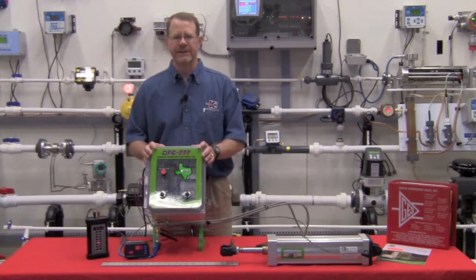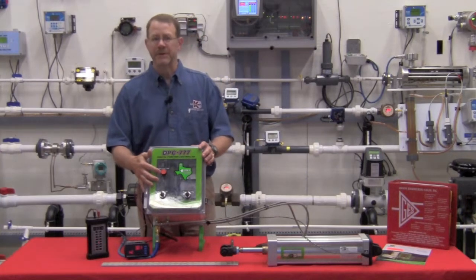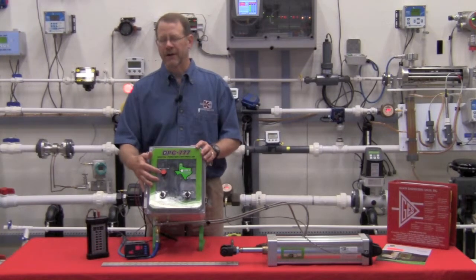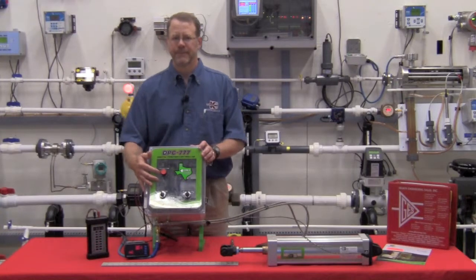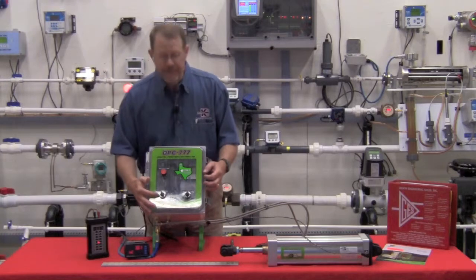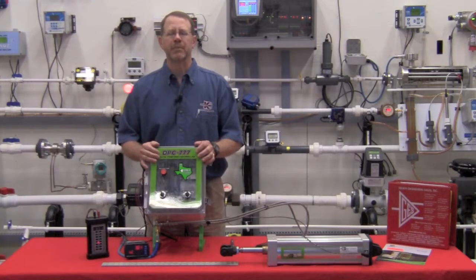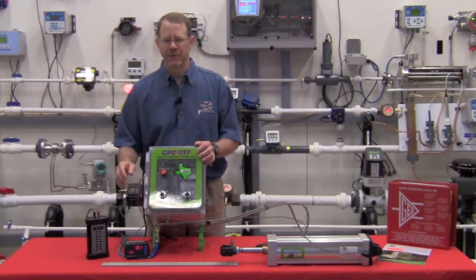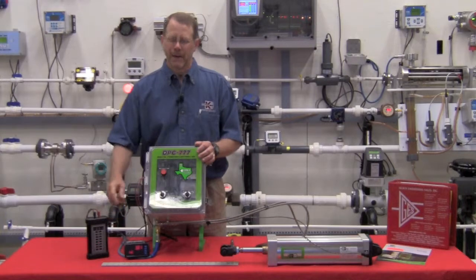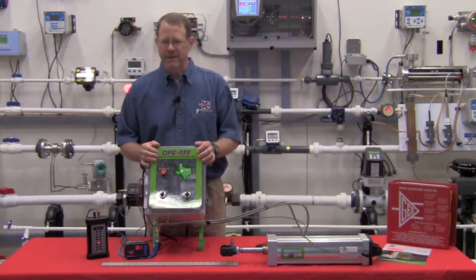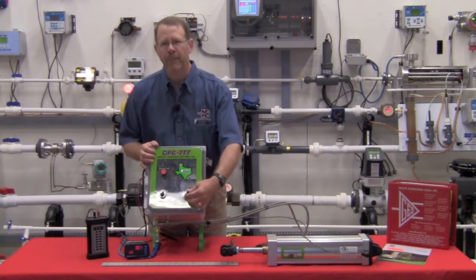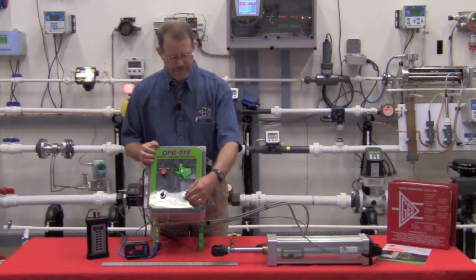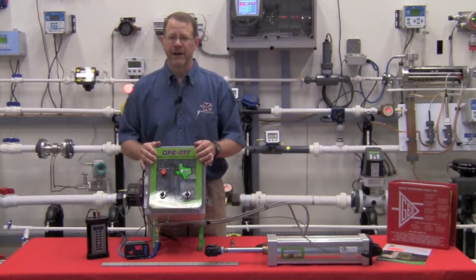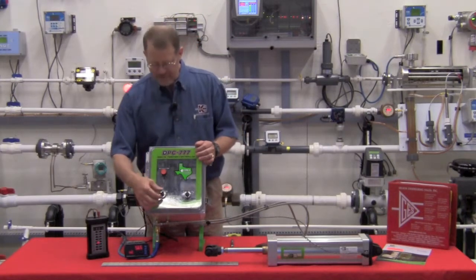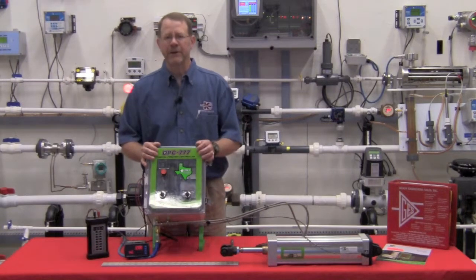Optional materials are available upon request. You will notice on the door of the DPC777 there is a reset button, push button, for the purpose of clearing a fault should one occur, without the need of opening the enclosure and introducing dust to the electronics. There's also the optional remote local switch and the open-close switch. These allow for complete operation of the JR linear drive at the field location. Placing the DPC in the remote position allows for the control via the DCS 4 to 20 milliamp signal. By switching to the local position, the 4 to 20 milliamp analog signal is interrupted from the DCS, and control is then given to the local operator in the field. This is very handy when you're doing your original setup and calibration of the drive. Now switching back to remote gives complete control back to the DCS.